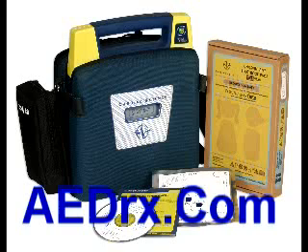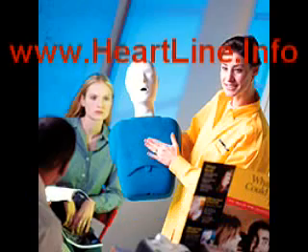Now, these batteries that we manufacture for the AED G3s are able to deliver up to 290 shocks at full energy. That's 360 joules. And even when the battery is low, we have a little reservoir cell inside our batteries which is capable of delivering an additional 9 shocks at full energy. So we want to make sure, even though hopefully nobody's going to be using the device 290 times, but not likely, just having that peace of mind, you know that battery is always going to be there when you need it.